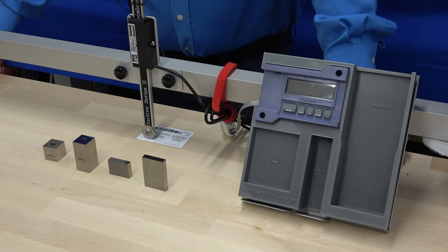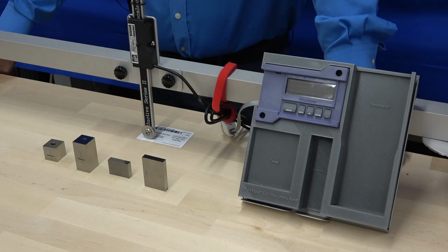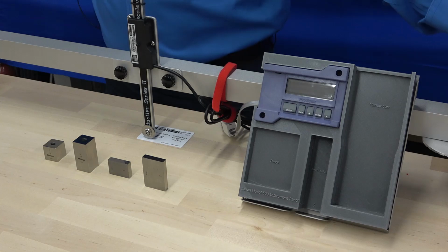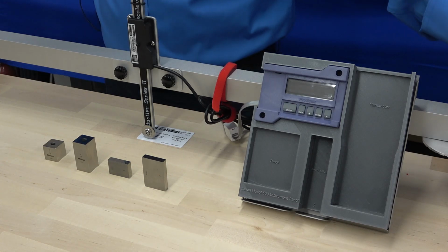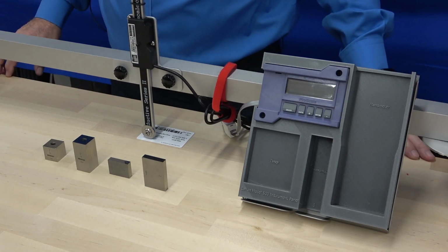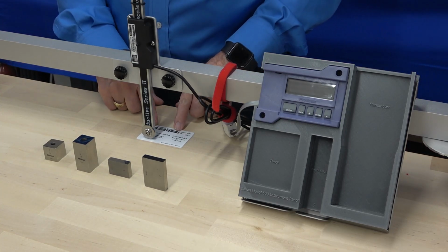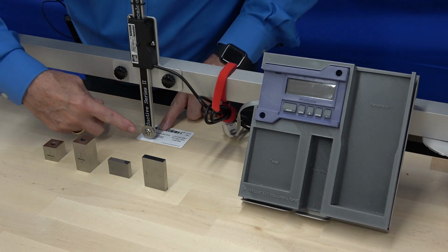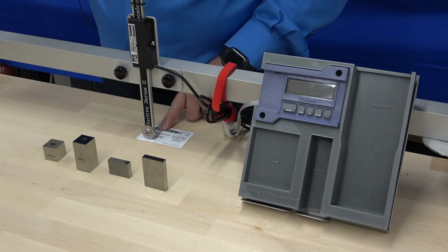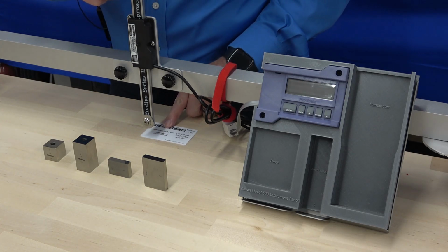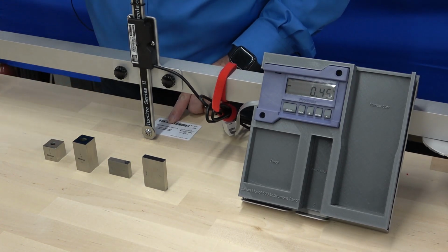I'd like to demonstrate today the technique that I follow to calibrate the deflection bar and sensor for the Canon Model 500 uplift chamber. You will need to have your bar assembled and on a relatively flat surface. You see there's no teetering or tottering of the device at all. You will also need something under the foot of the device that is consistent and level. That could be merely the top of a worktop surface.